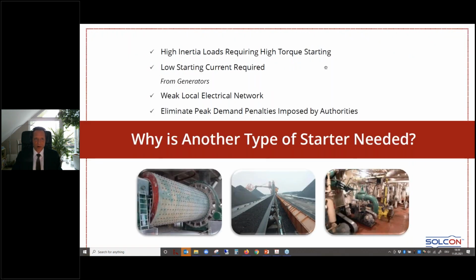As I said before, you can start high inertia loads with high torque demands. We can apply low starting current. Sometimes you have only generator supply and the generator itself is mostly deemed a weak network. And we can also eliminate peak demand penalties, which are imposed by municipalities and by authorities.